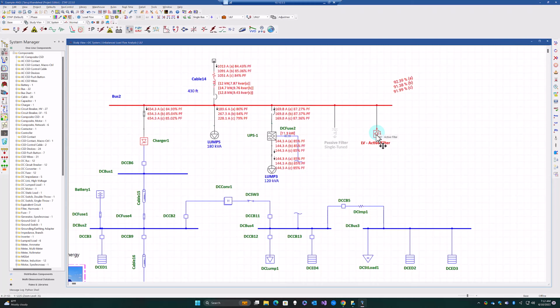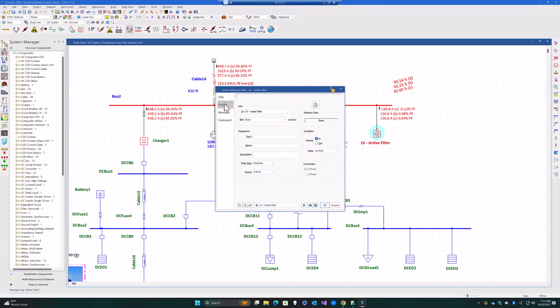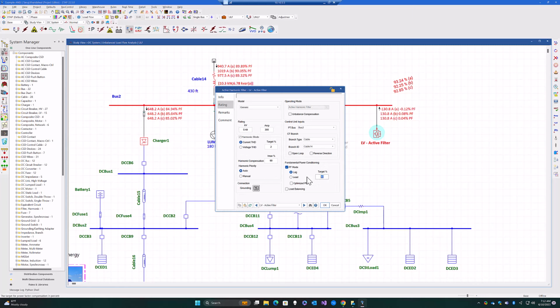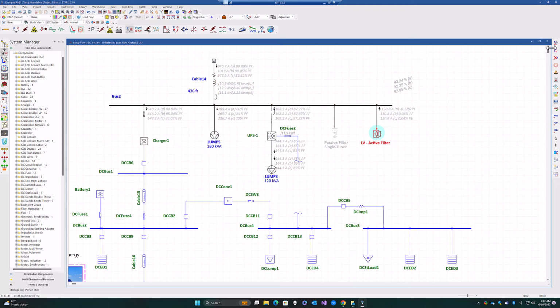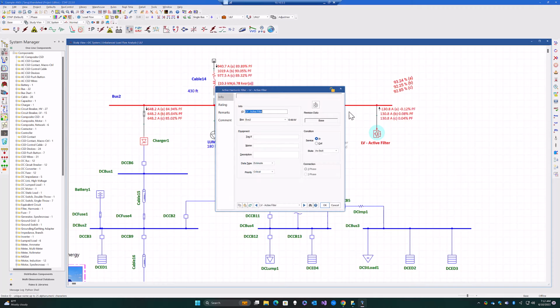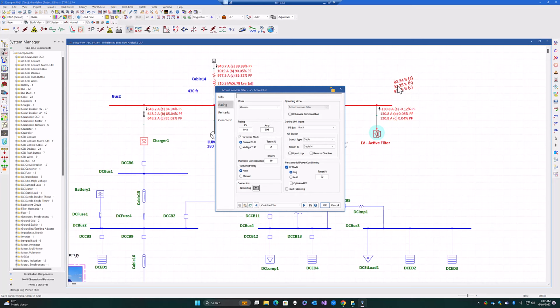When we run our simulation, we can see that we are nearly at 90% power factor using this particular objective. Could we achieve 92%? You can give it a shot and try it again. Bear in mind, we are at 130 amps per phase, and when you try to go higher than that, we have pretty much hit our limit of 300 amps, because again, we are at 300 amps at 100% nominal voltage at 480 volt. The voltage is not quite nominal, so we're able to go past 300 amps at a lower voltage. So 92% is not achievable, but 90% is.